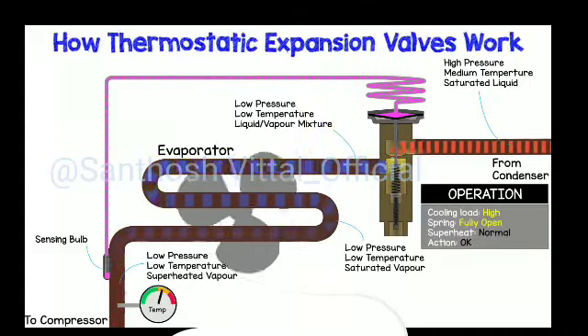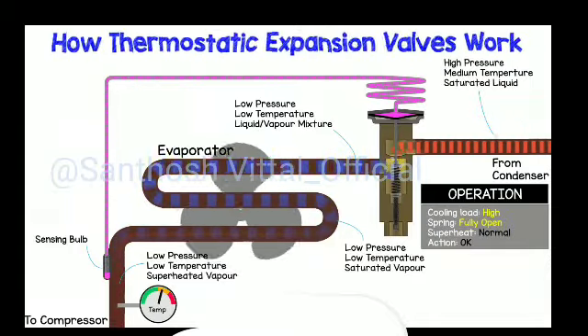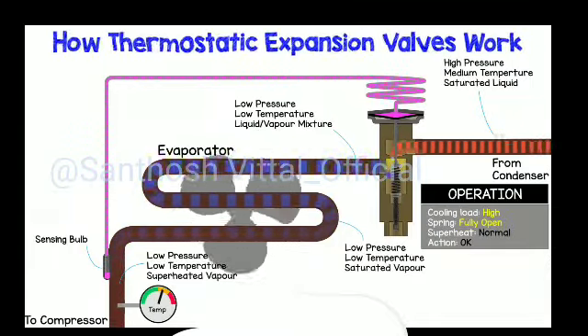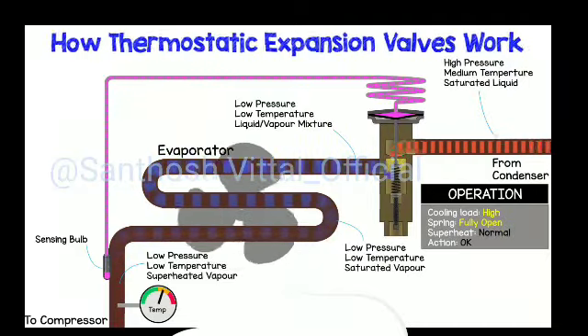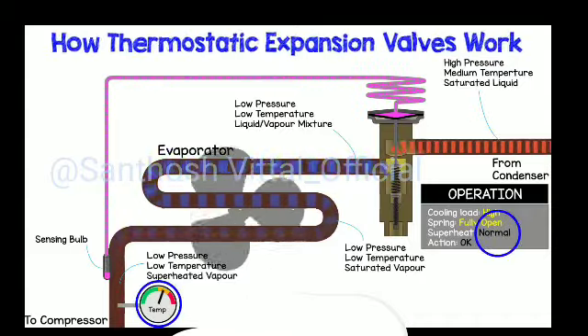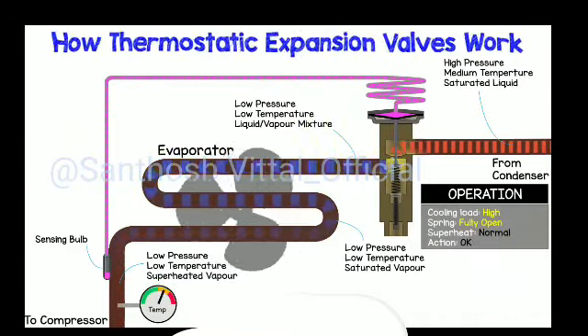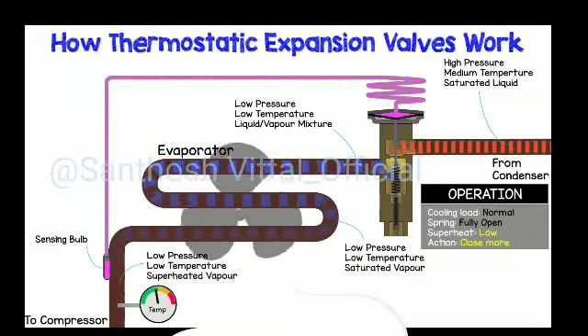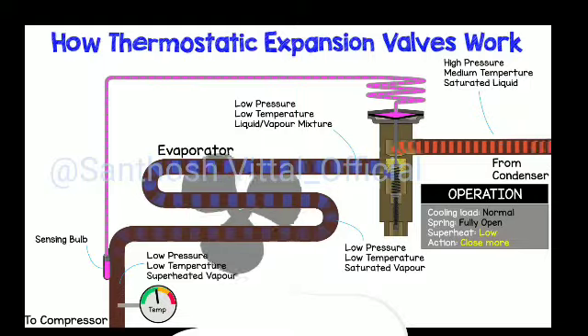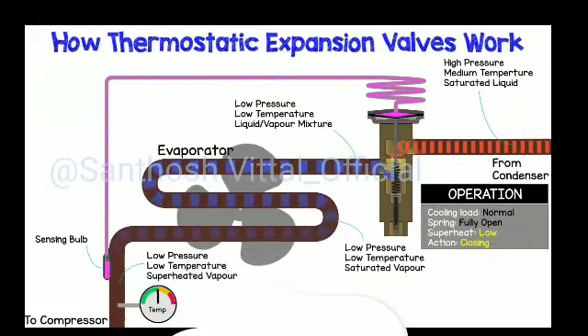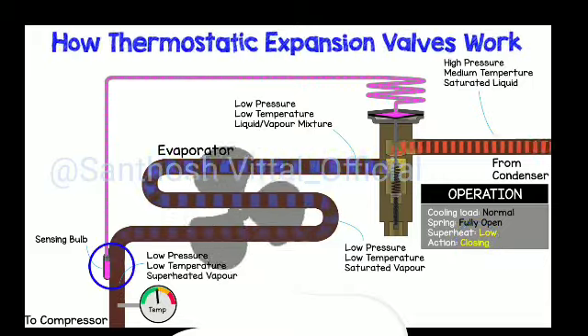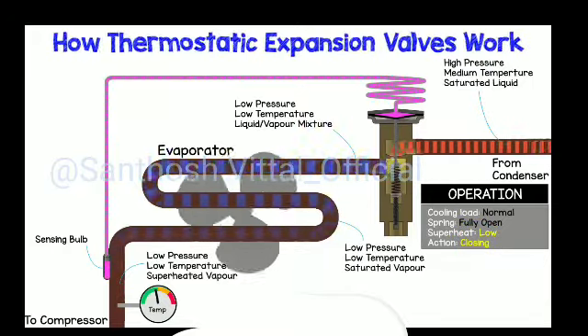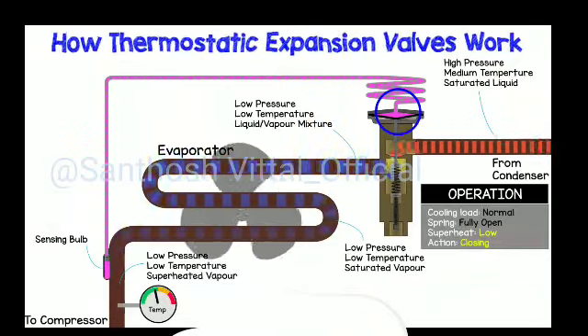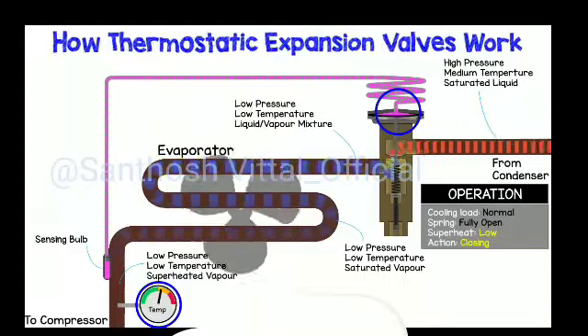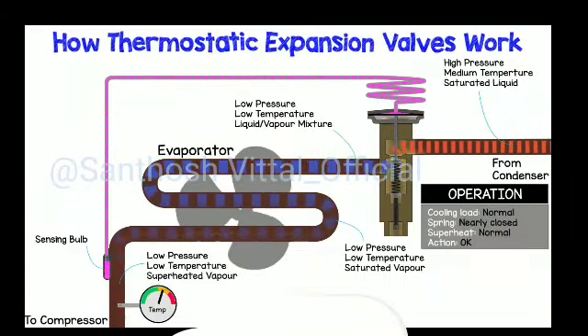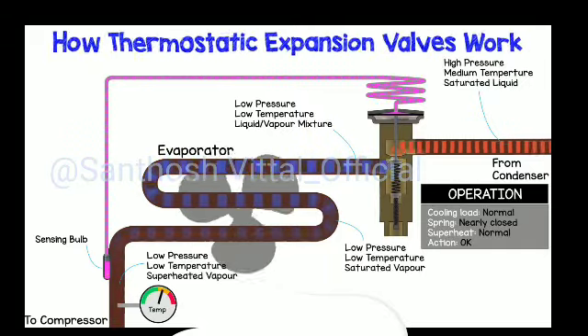The valve will adjust to find the correct position so that the force on the diaphragm is greater than or equal to the force of the spring pushing in the opposite direction. This allows the correct amount of refrigerant to flow, which decreases the superheat refrigerant temperature at the outlet, and the sensing bulb detects this and equalizes it. If the cooling load then decreases back to normal, the superheat temperature will reduce. The sensing bulb will detect this and will begin to reduce the refrigerant evaporation in its chamber. The refrigerant in the capillary then flows back towards the bulb, and the main valve begins to close. The superheat temperature will also start to rise as this happens. Eventually, the valve equalizes out, and the correct amount of refrigerant will flow through to match the superheat settings.